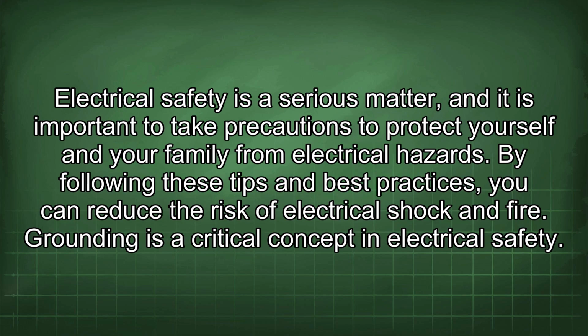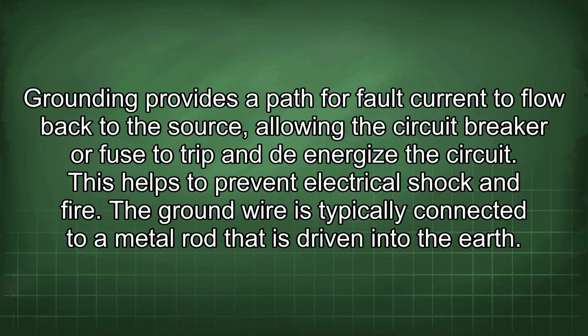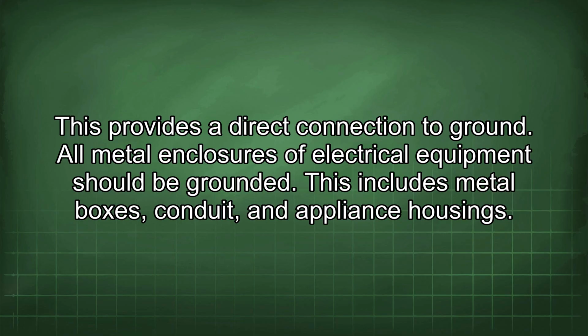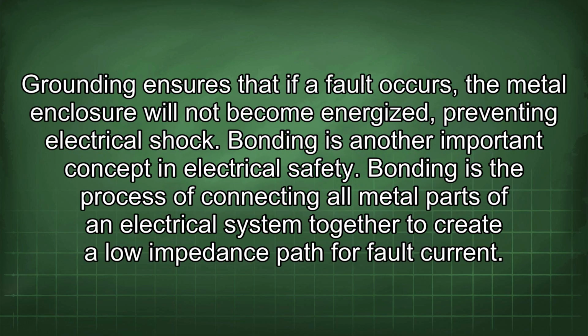Grounding is a critical concept in electrical safety. Grounding provides a path for fault current to flow back to the source, allowing the circuit breaker or fuse to trip and de-energize the circuit. This helps to prevent electrical shock and fire. The ground wire is typically connected to a metal rod that is driven into the earth. This provides a direct connection to ground. All metal enclosures of electrical equipment should be grounded. This includes metal boxes, conduit, and appliance housings. Grounding ensures that if a fault occurs, the metal enclosure will not become energized, preventing electrical shock.